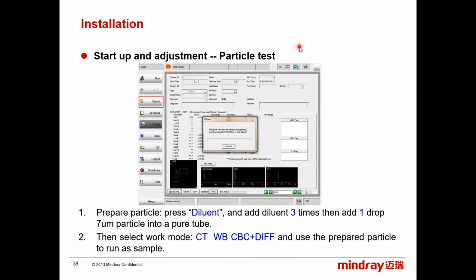It is also a very good tool to troubleshoot diff-related issues, because with these particles you eliminate the reaction cause. You know, because this one I do not need to lyse or anything. Okay, it will not be affected by, let's say, the reaction temperature or by the lysing, okay, by the chemical. So if this one is not good, it means you have a problem directly with the focalization, with the sheath. Okay.